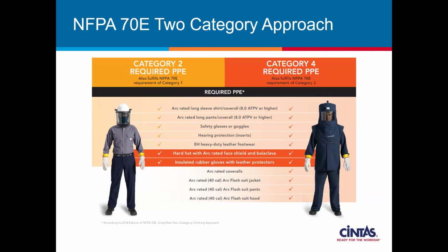NFPA 70E did us all a favor by creating the simplified two-category approach to PPE. This approach allows us to set up a solution to remove human error. Staff members do not need to think about what to wear, but rather use universal precautions and come to work in daily wear, shown on the left-hand side. In the rare occasion when an employee may be exposed to equipment greater than 480 volts, or labeled as category 3 and 4, they would typically need to add the taskwear items.